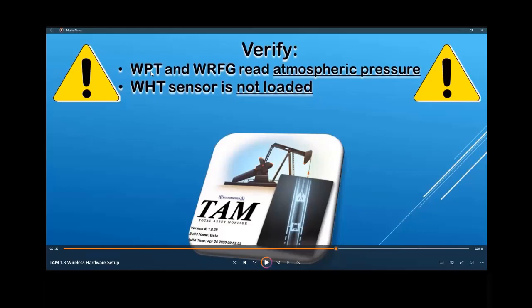Some people ask, how often do I need to get my zero offset? It's common practice for me to get a zero offset on each well that I go to. As I go throughout the day and the temperature changes, I want to make sure that I have an accurate zero offset. That zero offset, as we're about to see in the coming slides, is conducted with no pressure on the transducer. The well will be closed, the valve will be open, and the pressure on the transducer will be reading atmospheric pressure. You do not want to zero the pressure transducer with pressure on it.